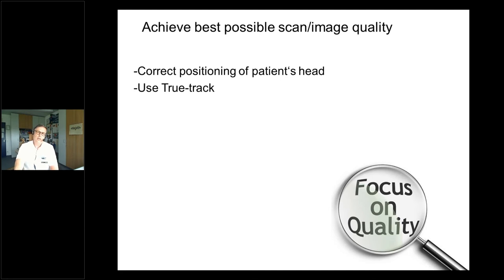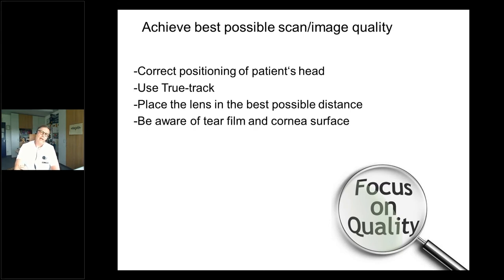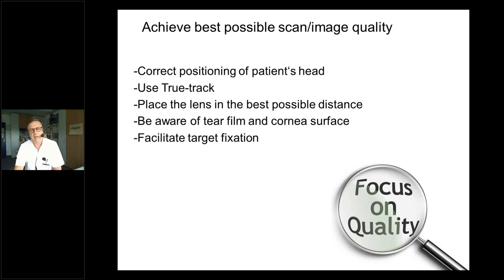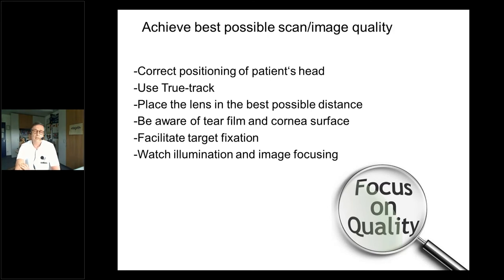Target fixation can be challenging in one-eyed patients — patience is required. Illumination is an issue for good image quality, as is image focusing. The patient needs correct positioning, correct scan positioning, especially when doing free circle scans centered on the optic disc. Always be aware of refractive errors, especially astigmatism — sometimes you need astigmatic correction glasses to get better image quality. Always check the segmentation with the B-scan.